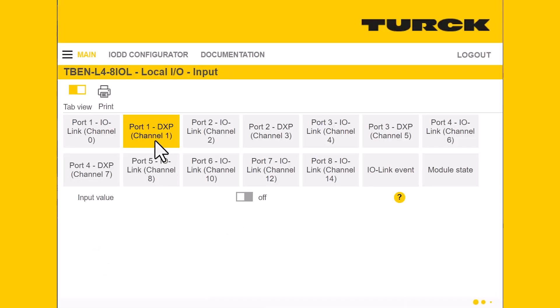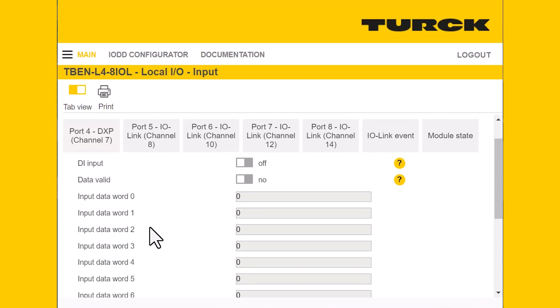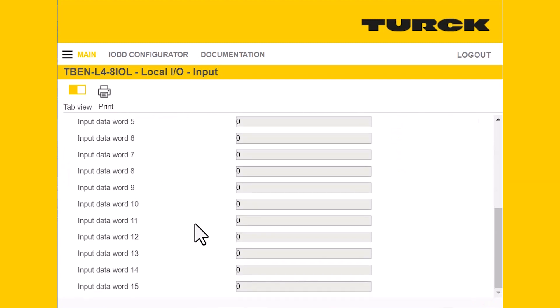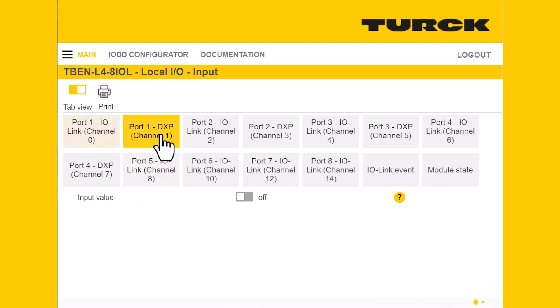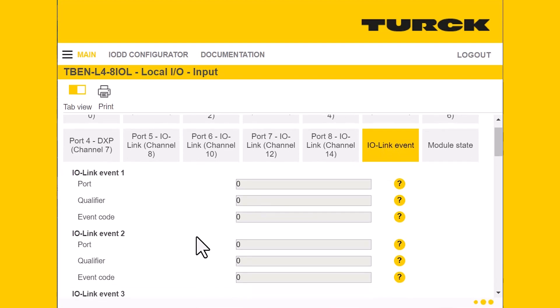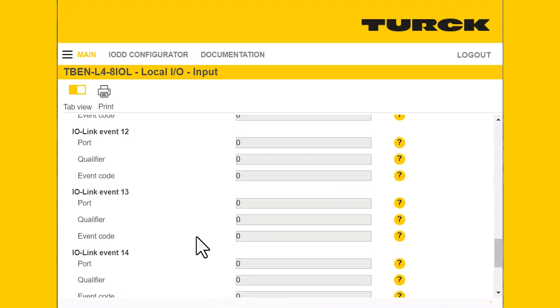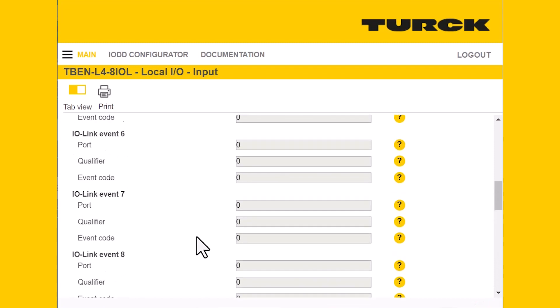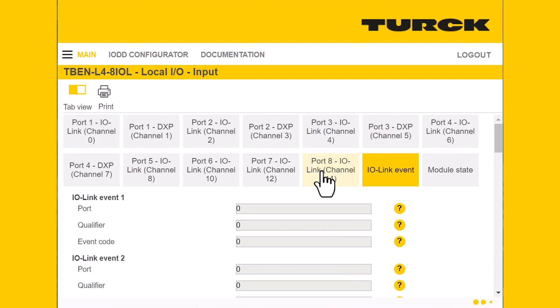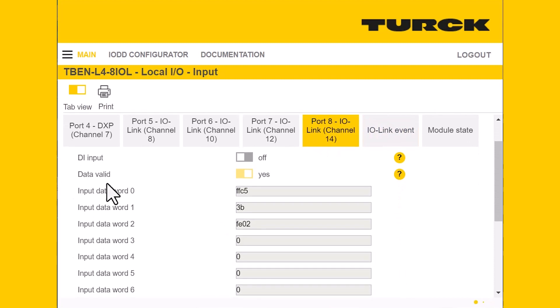Next, we'll go to the input tab. This gives you your input data broken up by words and will let you know if there's a digital input. If you are getting data, it will tell you that your data is valid. For your DXP, it shows whether or not you're seeing that digital signal. You can also go to the IO-Link event tabs to see any event codes. I'll go to port 8 where our device is plugged in — you can see the data is valid, and it's giving us our process input data in words, currently displayed in hex.